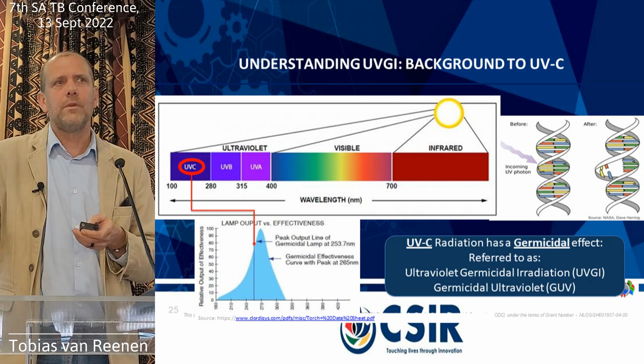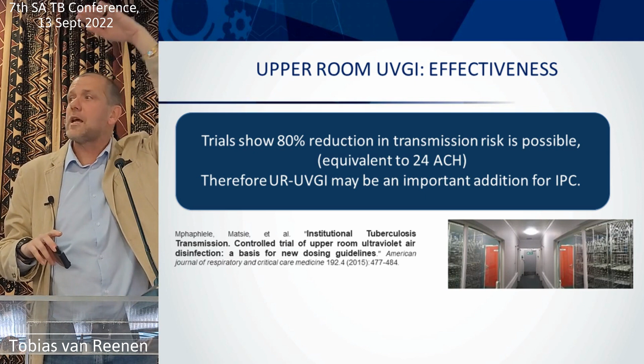Trials done in South Africa, seminal trials, I think a very important study, show that an 80% reduction in transmission risk is possible. That is equivalent to about 24 air changes in that study. So therefore, upper room UVGI may be an important addition to IPC. I spoke about 254 nanometer very briefly, and I spoke about 222. This study was upper room UVGI, which is 254 nanometer. The device we've got in the back of the room is a 254 nanometer. It has some inherent risks, which is why we keep that UV out of the occupied zone and in the upper room. So when we talk about upper room UV, it's that.